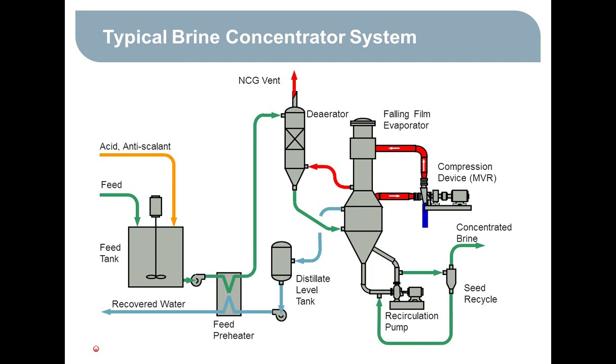So in essence, the MVR, or mechanical vapor compression system, is really an open cycle heat pump. We're taking low pressure water vapor and pressurizing it so we can use the heat to do the evaporation. So we recover all the latent heat of vaporization this way and reuse it. So it's very energy efficient. When the brine has been concentrated in the falling film evaporator, we have a seed recycle system, and we'll talk about seeding in a minute also. But basically, the seed recycle system takes the seeds out of the evaporator blowdown and sends them back into the evaporator, and the blowdown itself then goes to the next step in the process, which would be a crystallizer.